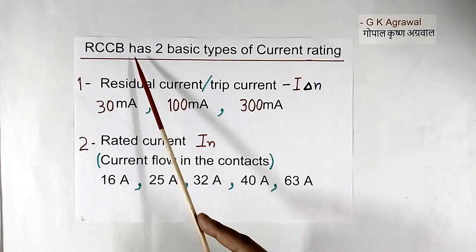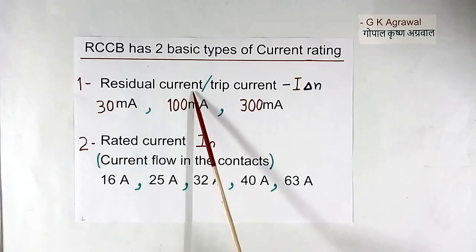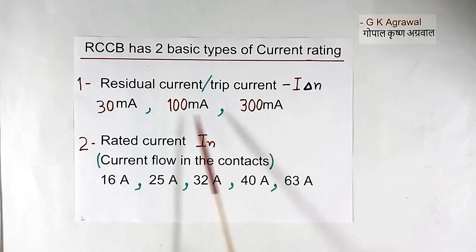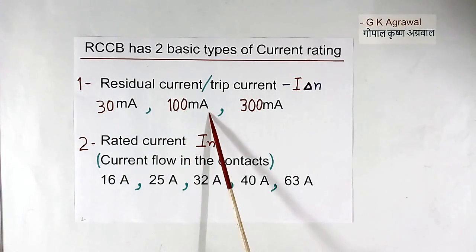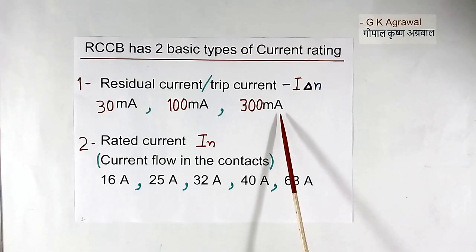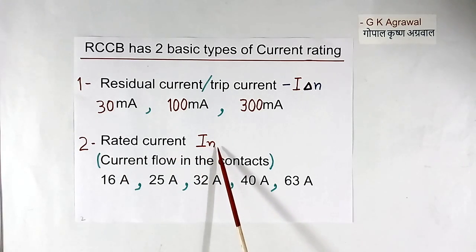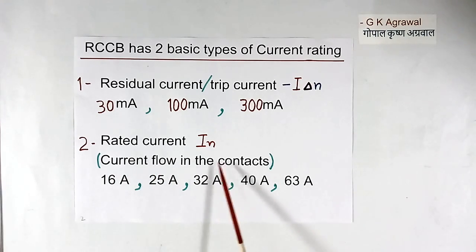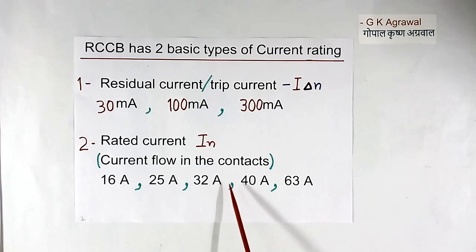Every RCCB has 2 basic types of current rating. First is the residual current, or trip current, which is also written as IΔN. This current rating may be 30 mA, 100 mA, or 300 mA. Second is the rated current, written as IN. This is the current which flows in the contacts, or the maximum current which can flow in the load. This may be 16 A, 25 A, 32 A, or 40 A.